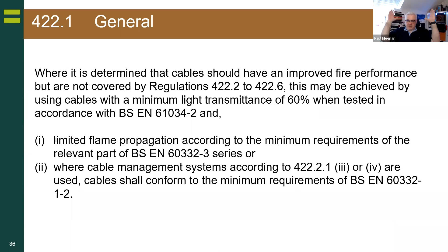Now, one of the key things that jumped out at me was this: where it's determined that cables should have improved fire performance but are not covered by regulation 422, so for instance in your emergency or protected escape routes, you may use cables with a minimum light transmittance of 60% when tested in accordance with 61034-2 and have limited flame propagation. And you immediately read this and go, oh, I've got to buy loads of standards. No, you don't. This is basically what it is.